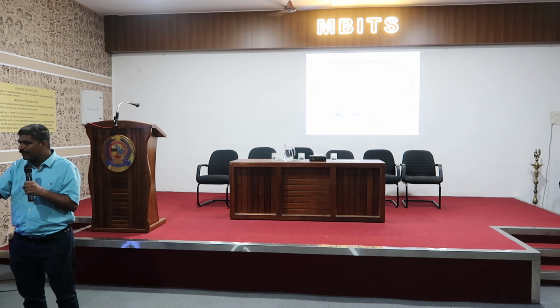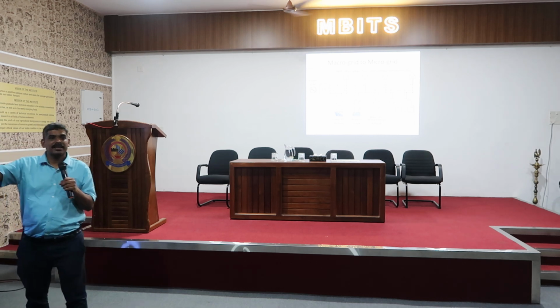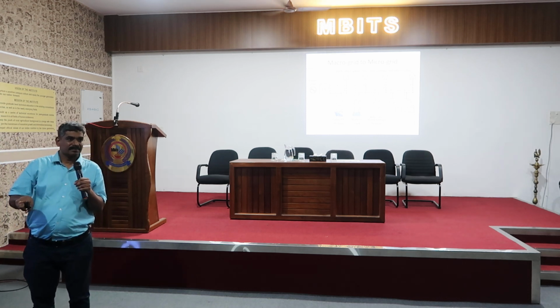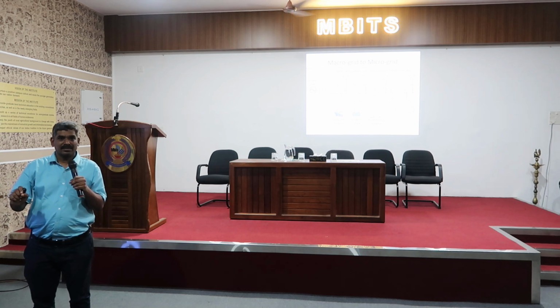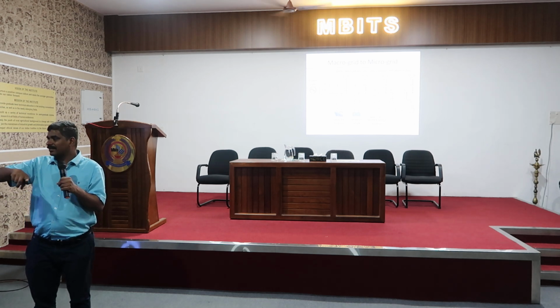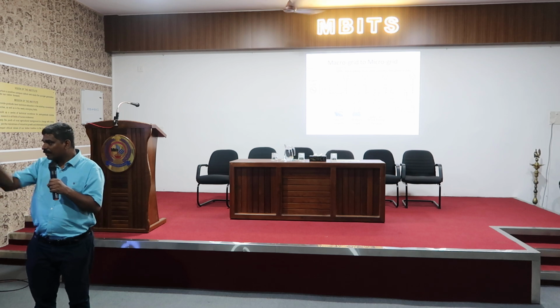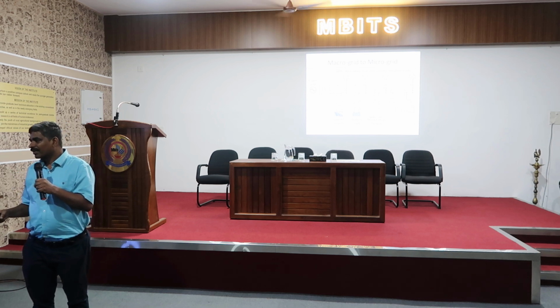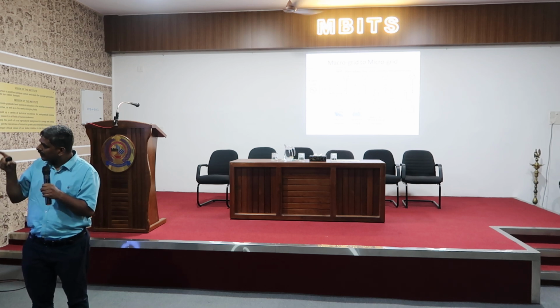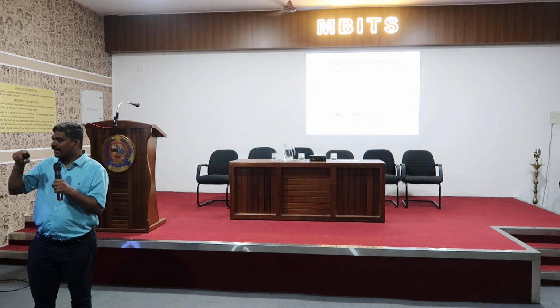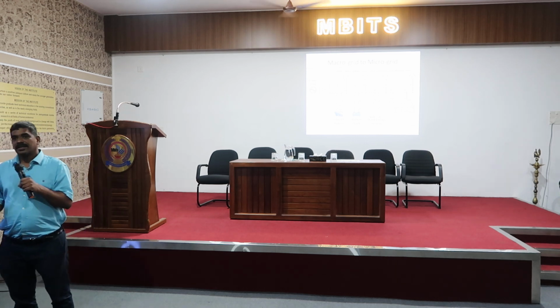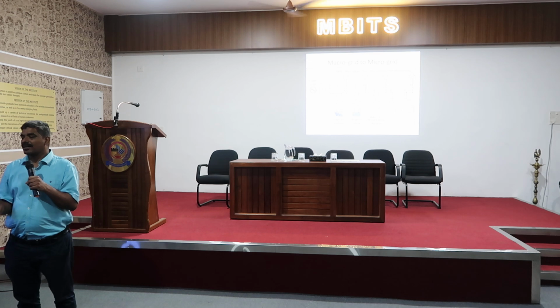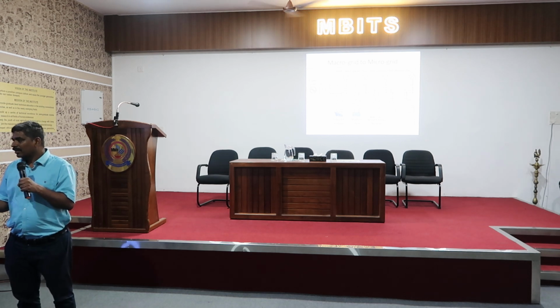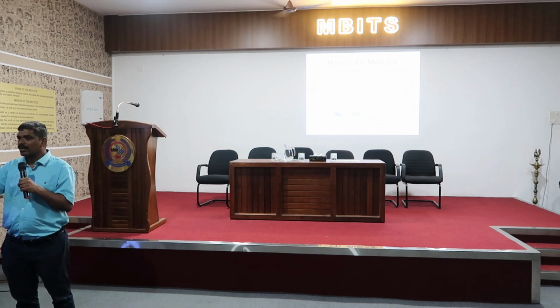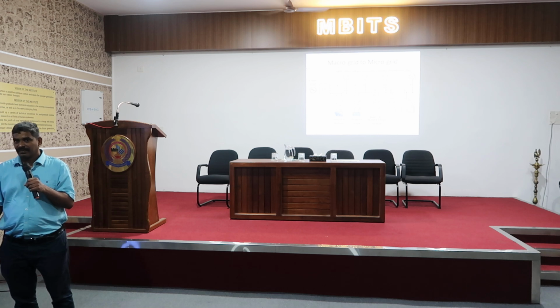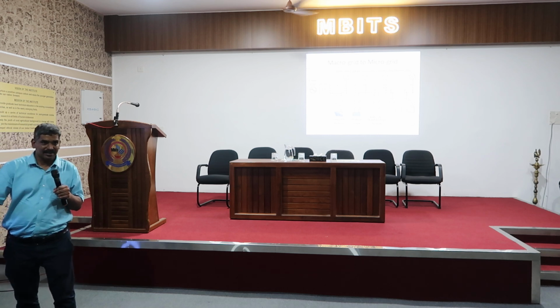This fifth order waveform will make a rotating field in the clockwise direction. Now you can imagine, so one is pulling in the other side, where the fifth order is pulling in the opposite direction. So what will happen? It will produce not only the reduction of speed, it will produce a pulsating torque. So if it produces a pulsating torque, what will happen to the rotor? Crack will be developed on the rotor, it will damage. Now you understood the problem very severely.